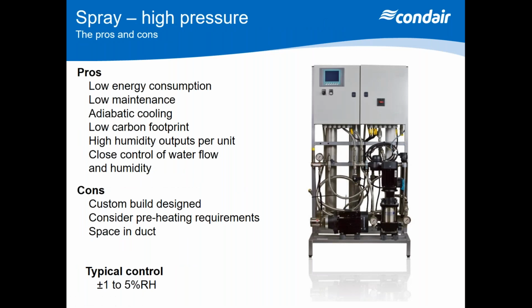So, high pressure spray. This is something that was brought into the field a few years ago now, but it's been around, and it's quite useful if you've got multiple areas that you want to humidify. What it does is spray very fine, good quality RO water at up to 80 bar. This pressurizes water out to a number of valve sets if it's on a ducted system, or a spray system that hangs down from the ceiling with a bed of air with a number of nozzles connected into a ring.